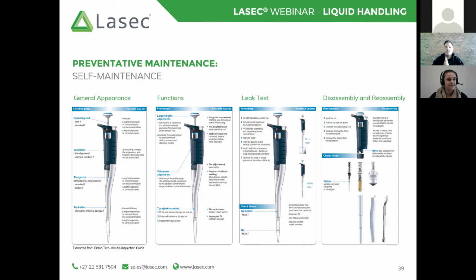All right, that's one function test for the volume. You can then, if the pipette allows you to change the volume in more than one place, for example, with these Gilson pipettes, you can change it on the actual push button. You can also change it on the thumb wheel. It's important to check both of those.